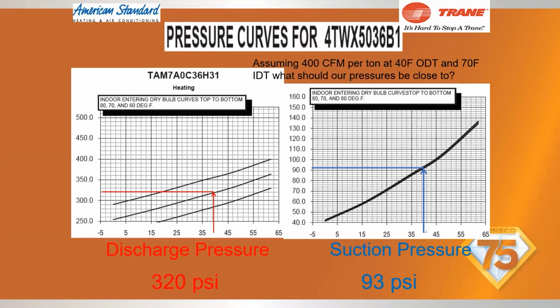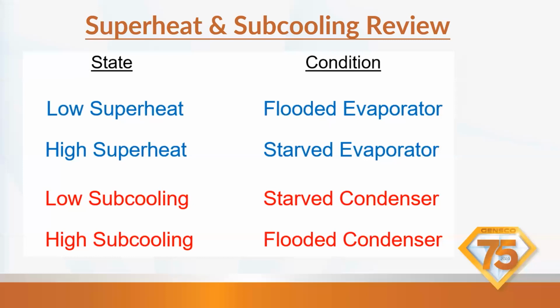So if you're at a 40-degree subcooling in heating, it's possibly overcharged. Our pressures might be above our lines, right? So we would want to remove refrigerant, and 8 ounces seems to be a magic number when adding or removing refrigerant. The variable speed systems are a little bit more temperamental to refrigerant change. So 8 ounces is a good amount to start with removing or adding.